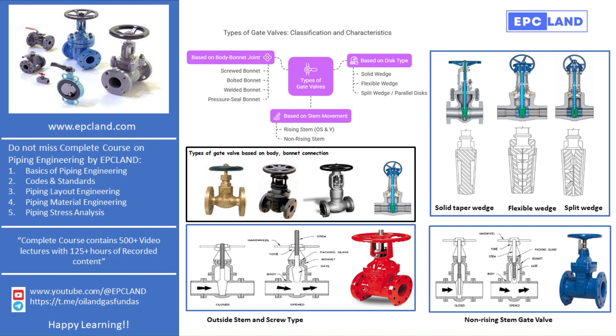The flexible wedge is also a one-piece disc but has a groove or cut around its edge. The cut allows the disc to flex slightly, which helps the valve seat better and improves tightness. Flexible wedges are especially useful in steam systems. When steam causes the pipeline to expand due to heat, the flexible wedge adjusts itself, preventing thermal binding. However, one downside is that fluids can collect in the groove, which may lead to corrosion over time.